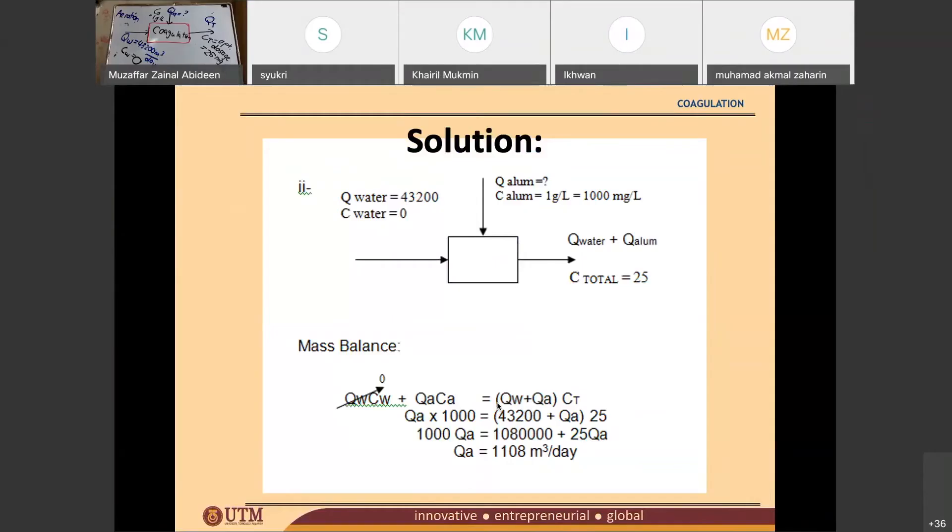So this is basically a mass balance. Q water times C water plus Q alum times C alum is equal to Q water plus Q alum times the optimum dosage of 25. So they would like to find out the Q alum or QA. Just by solving this equation, eventually you will get Q alum to be 1,108 meter cube per day.